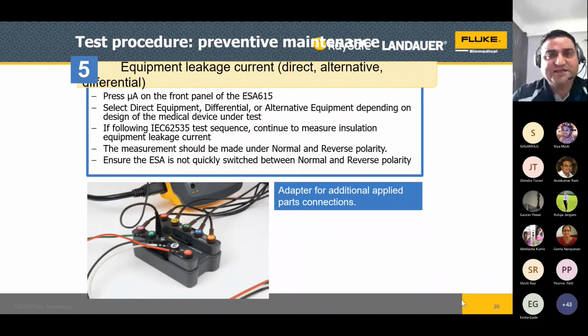Again, same as I said, equipment leakage currents. You can perform the leakage currents, the touch currents are there. All those currents you can verify, you can check, and you can measure all those things. And one more thing here, what you can also do is you can make a single fault also. See, what we are doing is we are doing the testing in a normal condition also, but you can make neutral as a phase and vice versa. You can reverse the polarity, then still your equipment should give the readings.